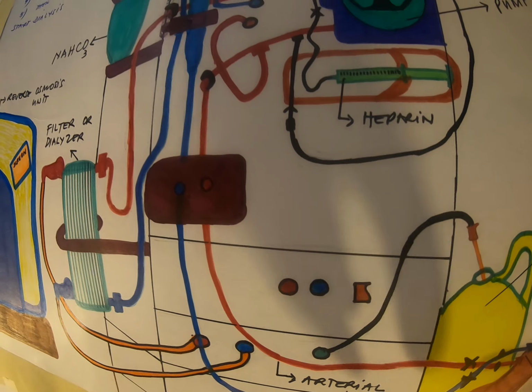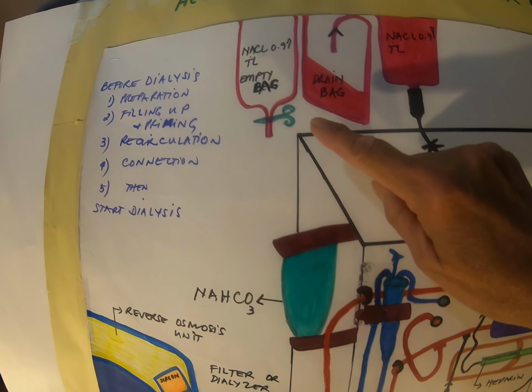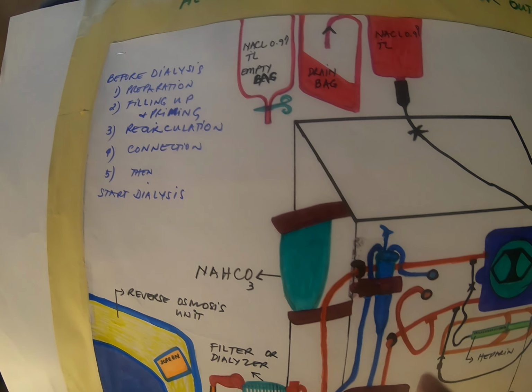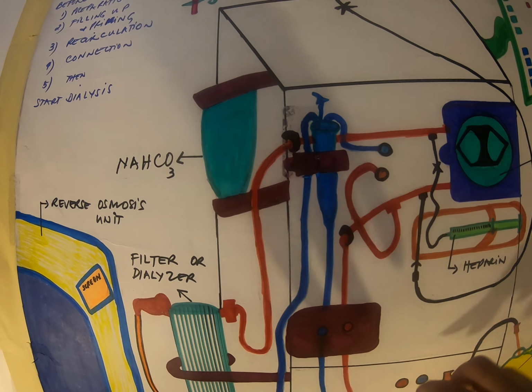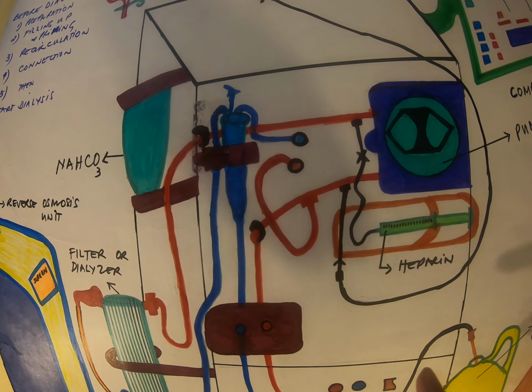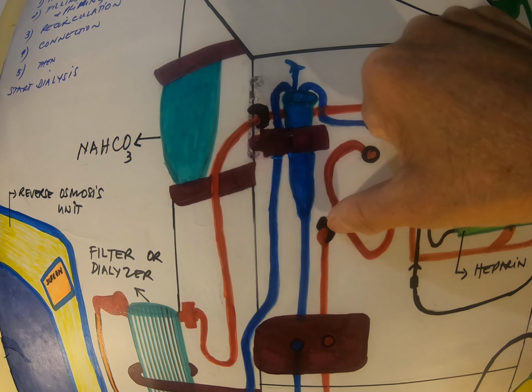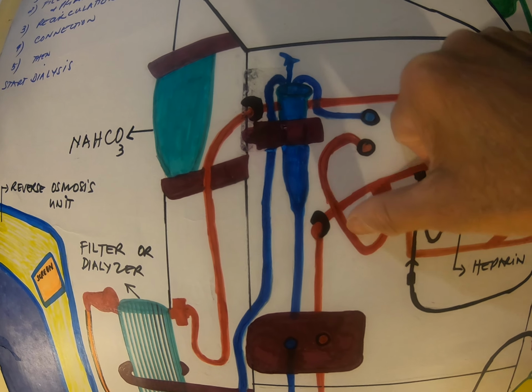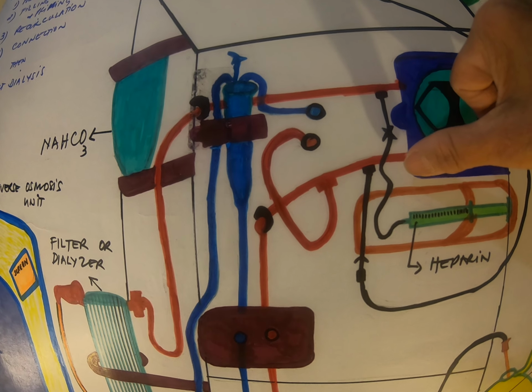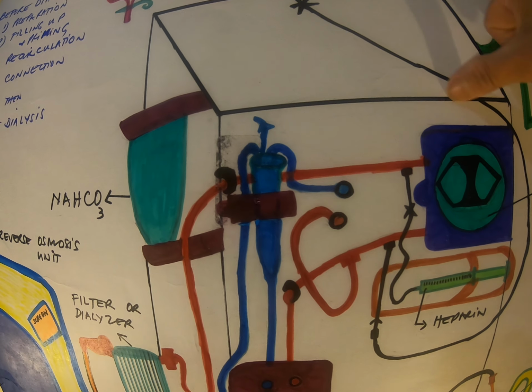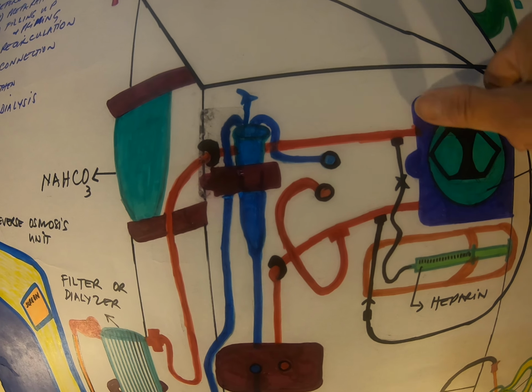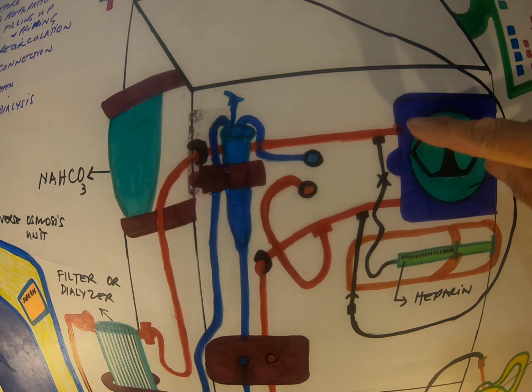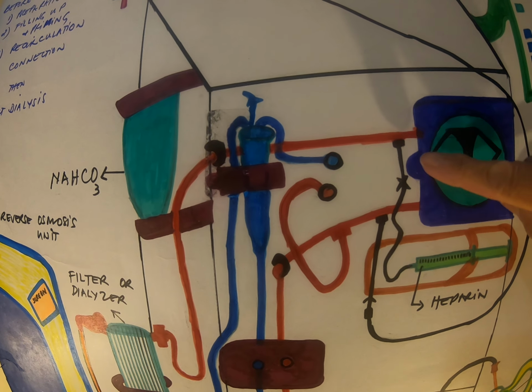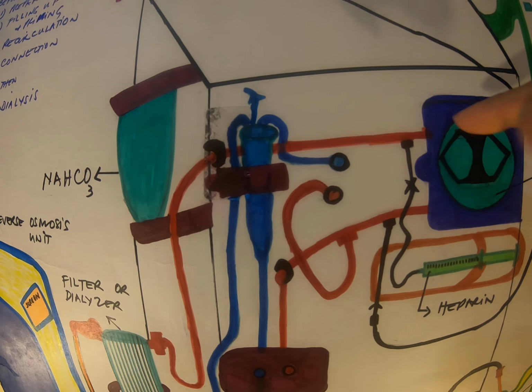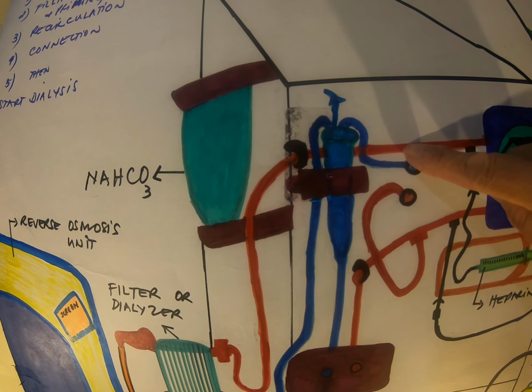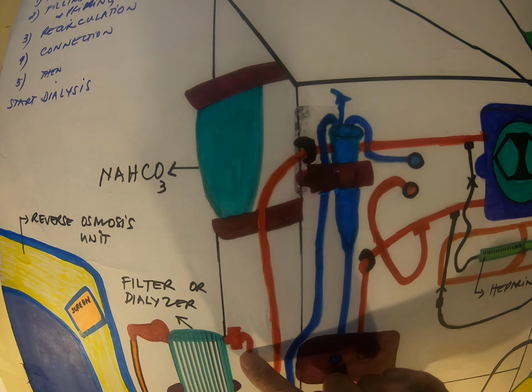So this arterial tubing is connected to the 1 liter of sodium chloride. This is the tubing, and it is supported by this clamp, and it goes up here. There is a little bloodline guide, and there is this transducer connection. This is a transducer, and this is the sodium chloride. It's up in here, it's clamped, and that will be primed later. And there is the blood pump in here. After the blood pump, we have this heparin pump, right here, that is the heparin port. And that arterial tubing extends down here, and at the end is a connector to the dialyzer.